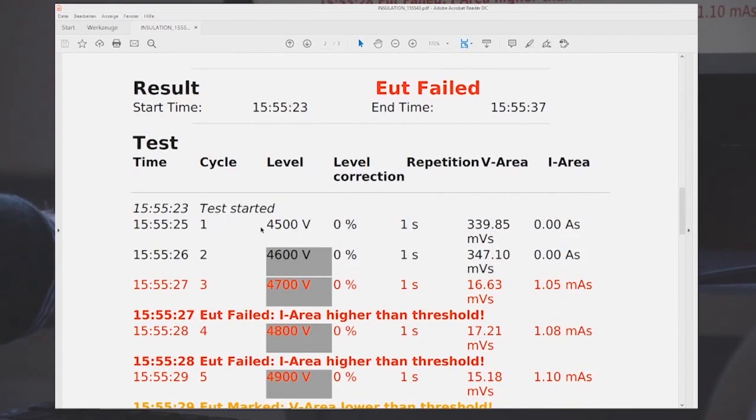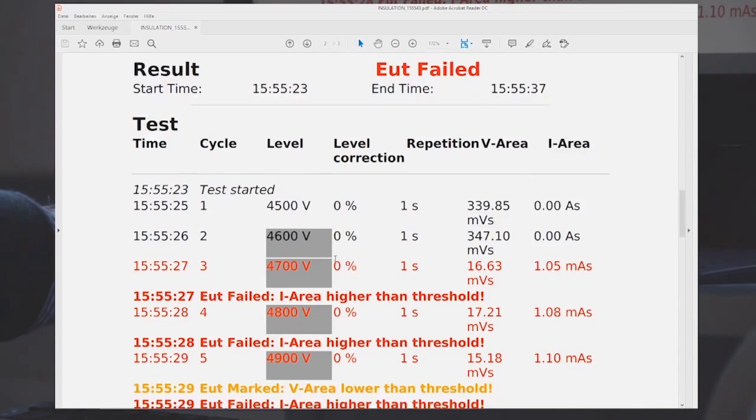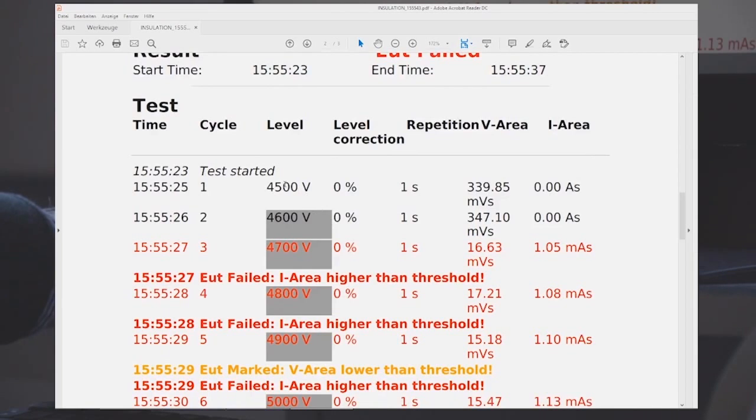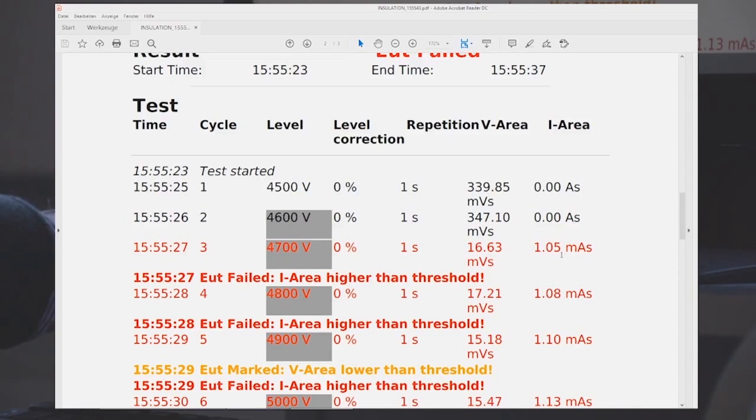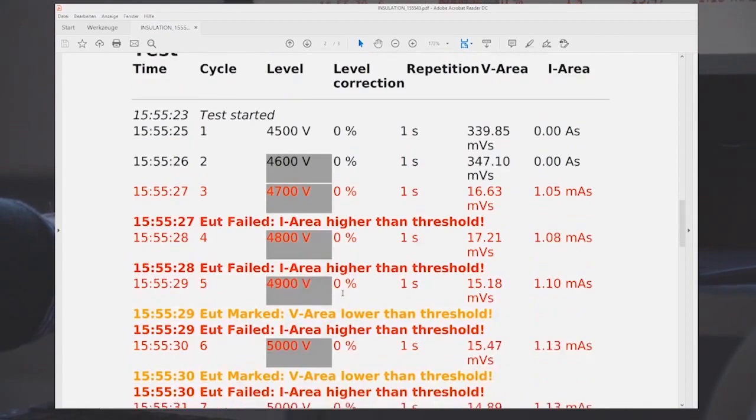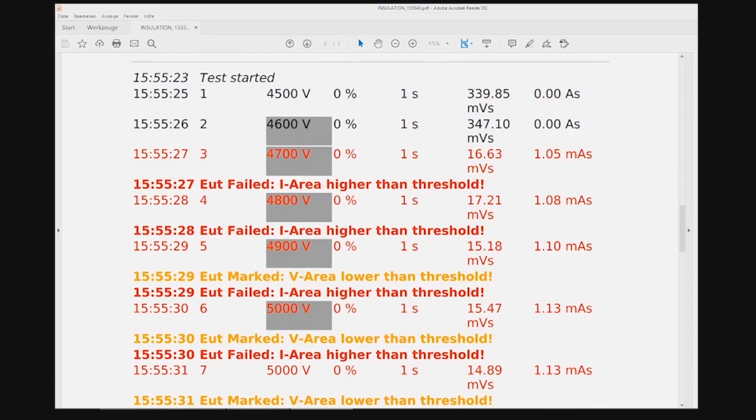Here the first pulse, 4.5 kilovolts. We have the voltage integral and the current integral. The current integral was zero, there's no breakdown. And then using the ramp function we increased from 4.5 in 100 volt steps, and at 4.7 kilovolts the test object broke down. We see the voltage integral has decreased and the current integral has increased. And we set it so that a warning would be shown that the EUT failed because the current integral was higher than the predetermined threshold.